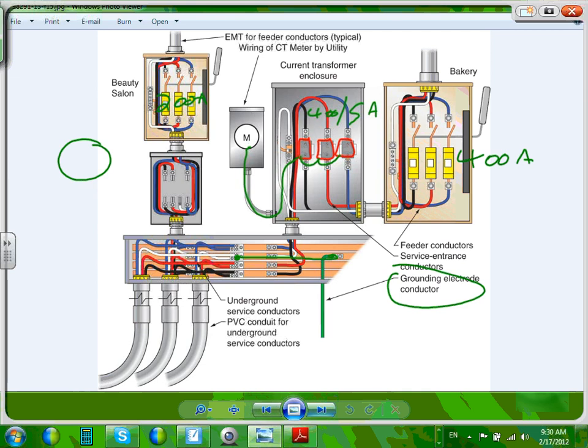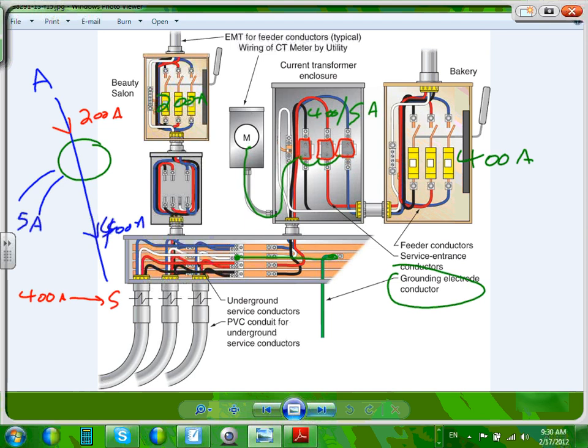So here's my CT, it's basically a current transformer, and here's the current. So if there's 400 amp in phase A, this is phase A, this CT cabinet will see it as 5 amps by design. Okay? Now, suppose this is 400, suppose I'm pulling only 200 amps here. So 400 goes with 5, so you can do proportional, 400 amp to 5. If you have 200 amp, what do you get? Right? 2.5 amp.